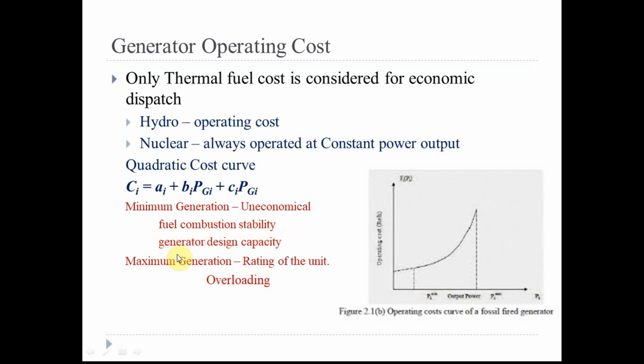Operating below the minimum value is considered uneconomical. Two factors that determine this minimum generation value are fuel combustion stability and generator design capacity, both dependent on the unit design. The maximum generation limit is dependent on the rating of the unit — for example, a 2 MW unit can generate at most 2 MW; anything greater is considered overloading. Every generating unit must be operated within the limits of P-minimum and P-maximum.